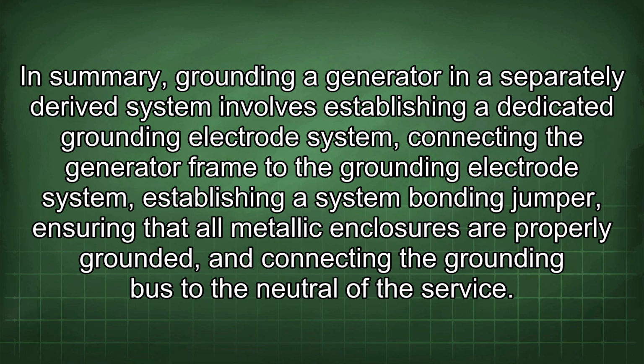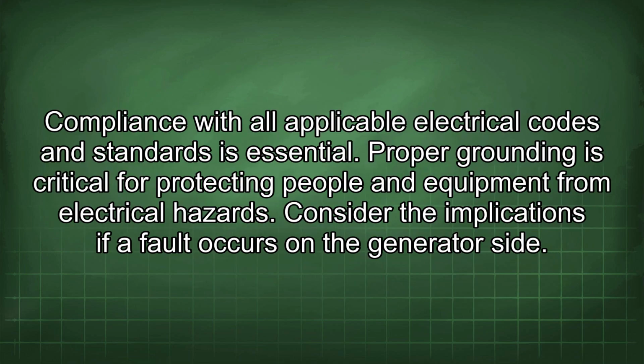In summary, grounding a generator in a separately derived system involves establishing a dedicated grounding electrode system, connecting the generator frame to the grounding electrode system, establishing a system bonding jumper, ensuring that all metallic enclosures are properly grounded, and connecting the grounding bus to the neutral of the service. Compliance with all applicable electrical codes and standards is essential. Proper grounding is critical for protecting people and equipment from electrical hazards.